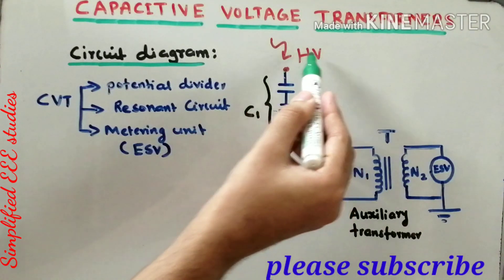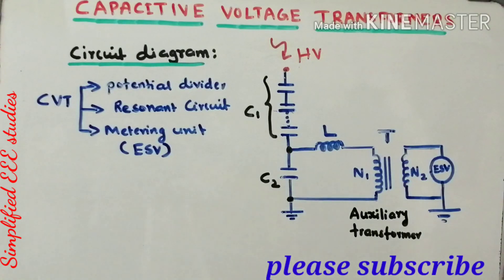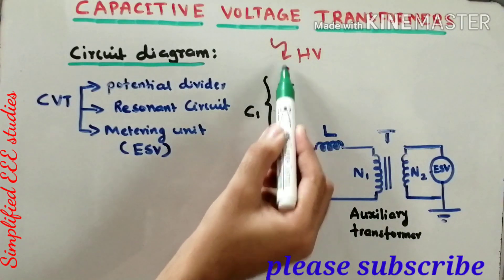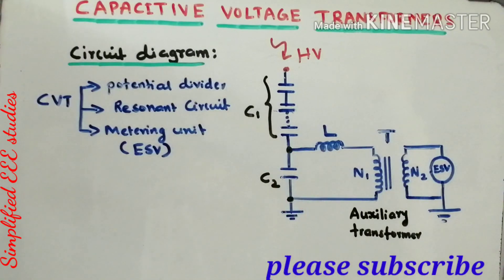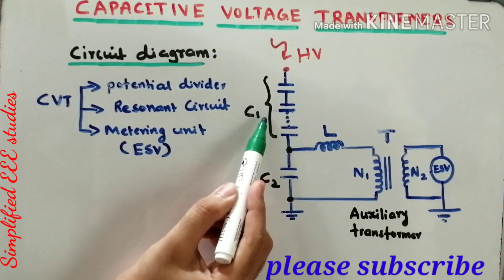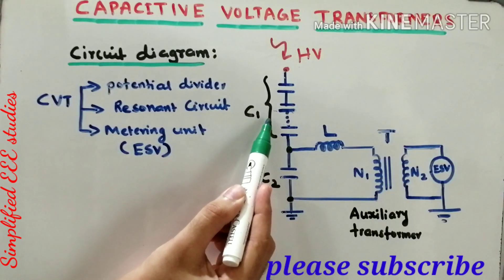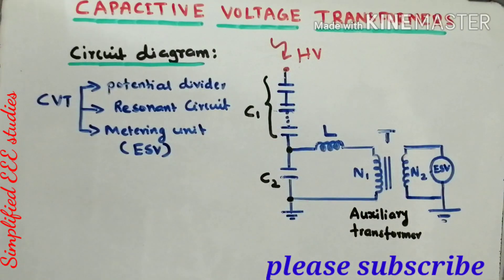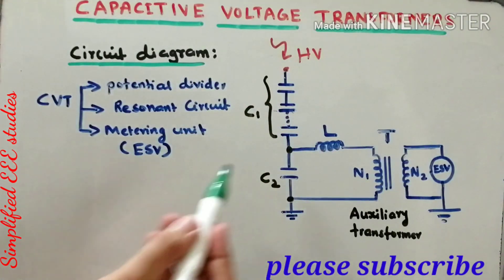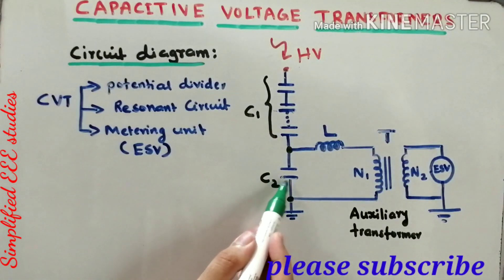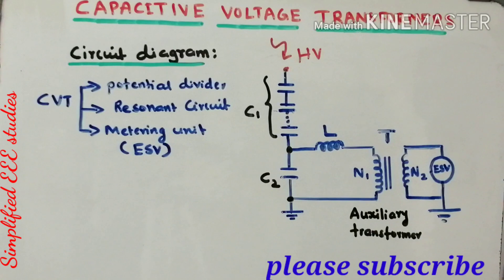The total high voltage, which will be above 100 kV, is divided with the help of a capacitive voltage divider. The segment from the top to C1 belongs to the high voltage arm, and from that point to ground belongs to the low voltage arm. For the high voltage arm, the capacitance value is very low because it is connected in series — therefore high voltage appears across it. For the low voltage arm, the capacitance value is high, maintaining a low impedance path, so low voltage appears across that point.